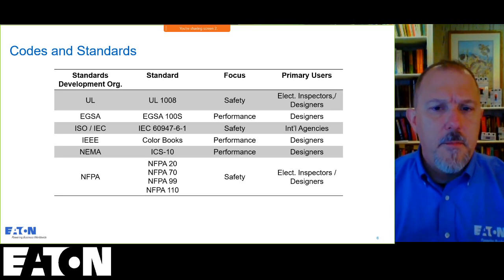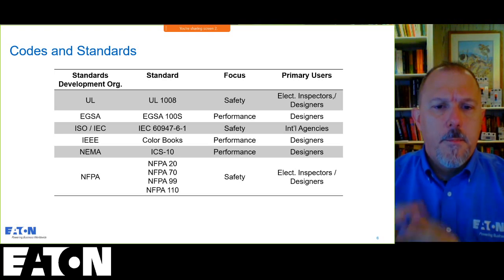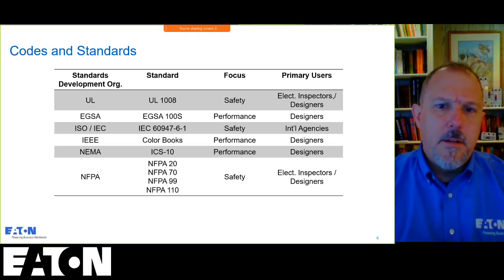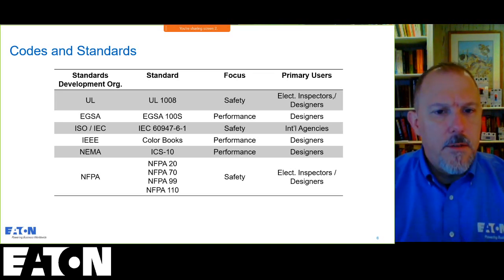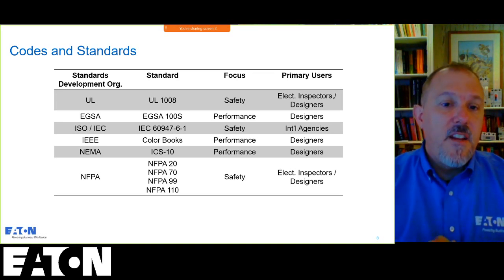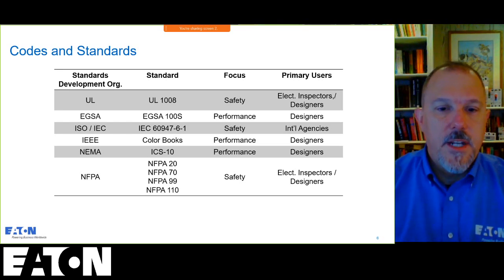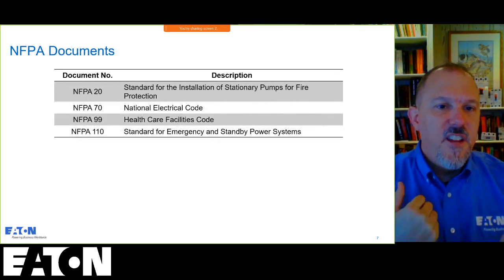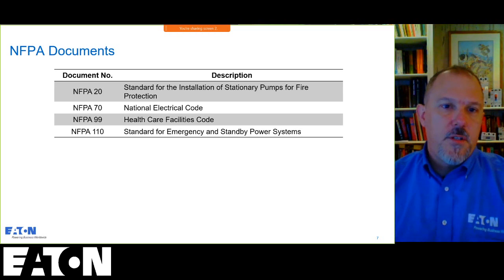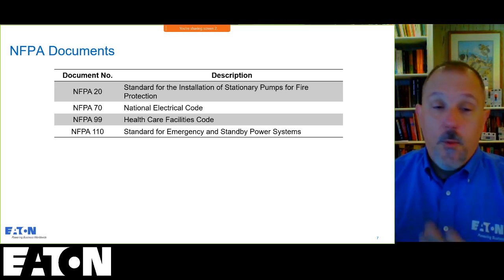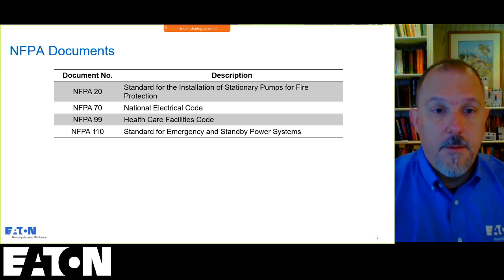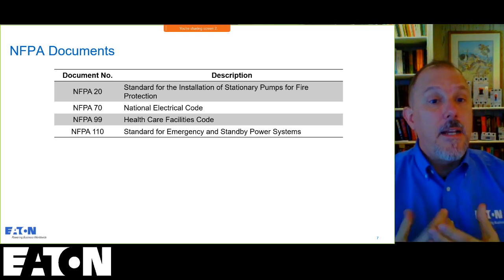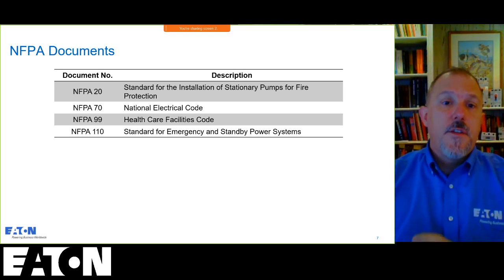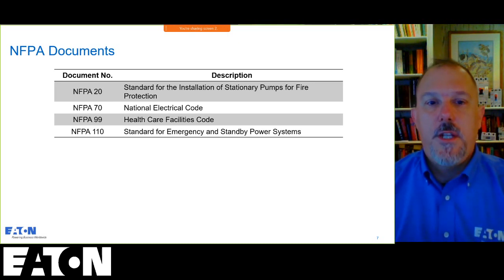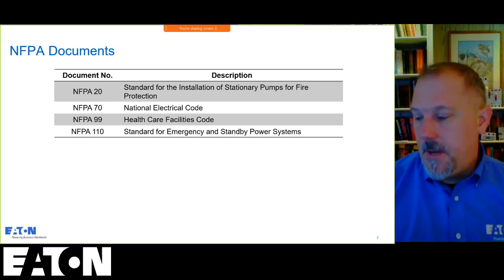And then there's the NEMA document with a performance focus, ICS 10. I believe that might be a free download. I don't know if I downloaded that one. And then you have obviously the NFPA documents 20 and 70, which I have on this next slide. NFPA 20 is for stationary pumps for fire protection. We all know the National Electrical Code. We love that document, right? And then you have NFPA 99, which focuses on healthcare facilities, and 110, which is your standard for emergency and standby power systems.